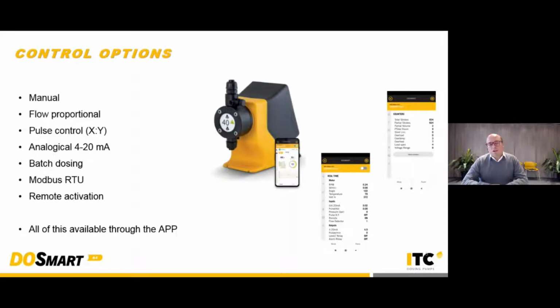We can work proportionally to the flow. We have a flow meter connected to the pump, and based on the reading we have on the pipeline, the dosing pump will modify its output in order to fix the proportionality to this flow. We can also work proportionally in a different way. In the mode we call XY, we are receiving pulses, which are X, and we are injecting strokes, which are the Y. And we can work with any combination of X and Y.